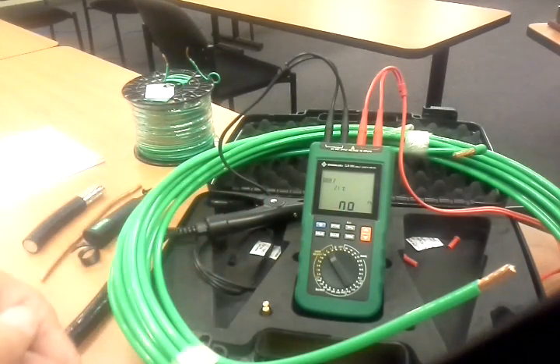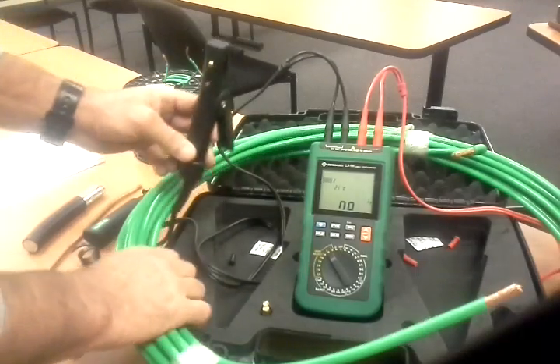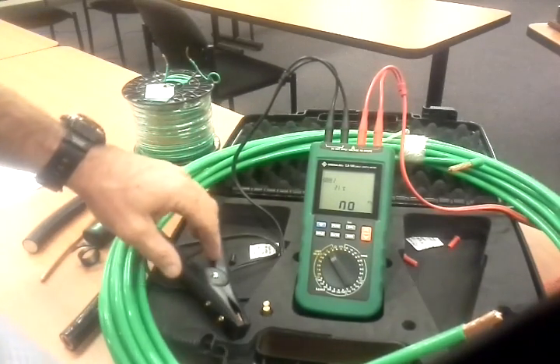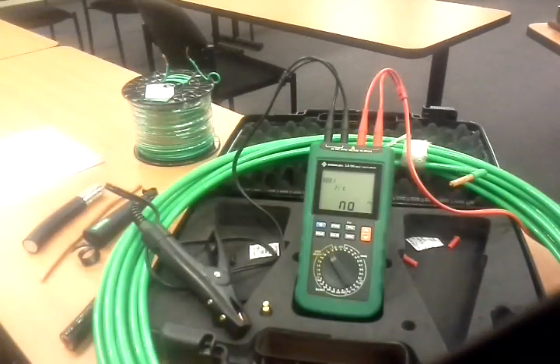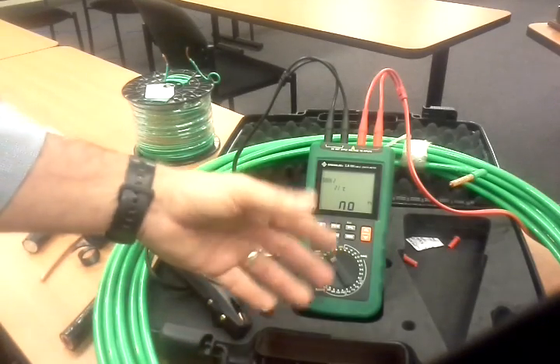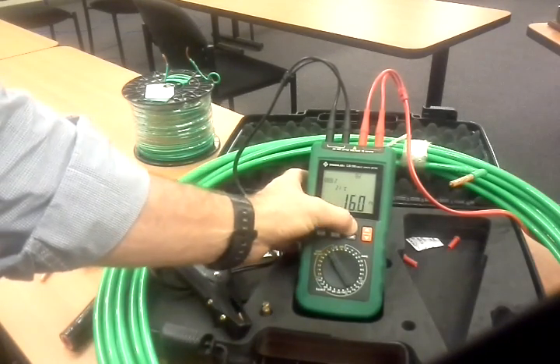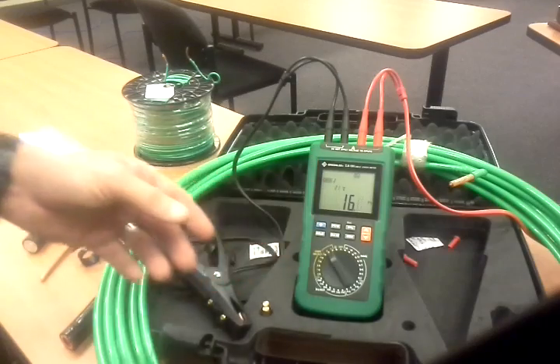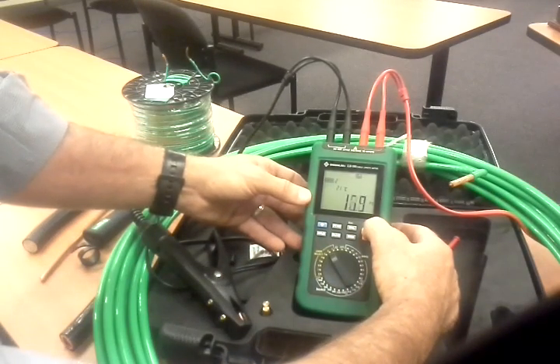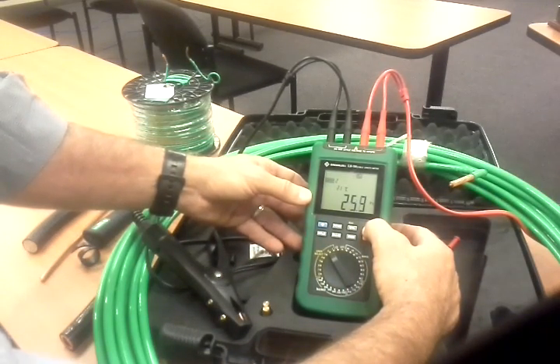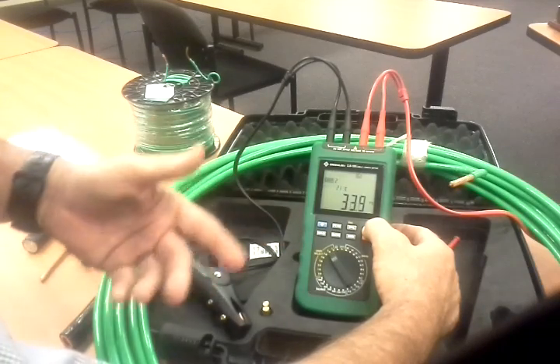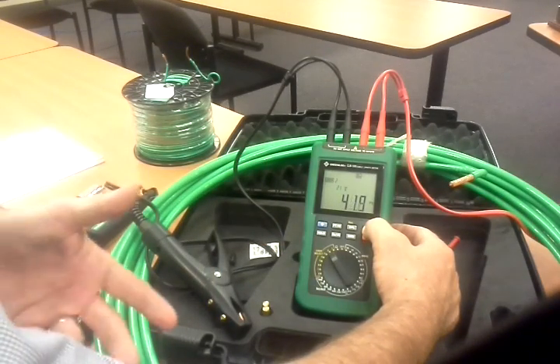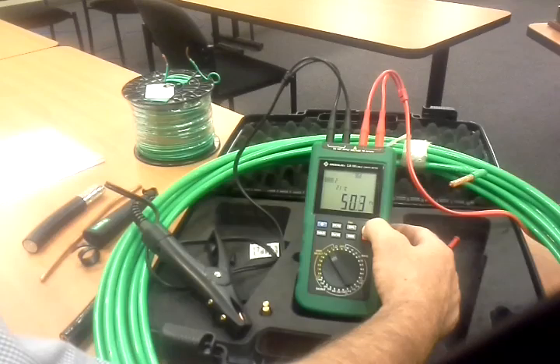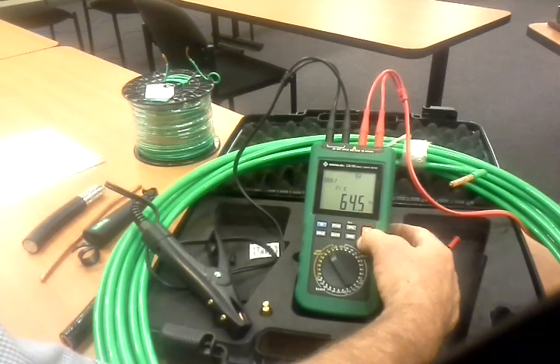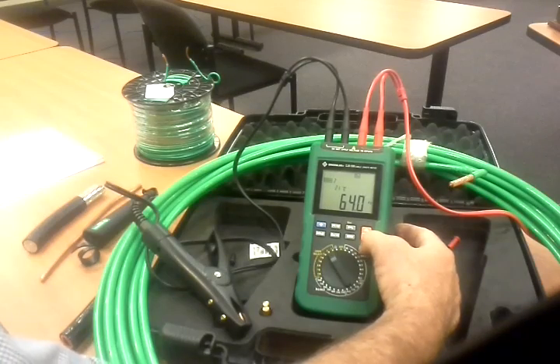So in order to set this now, all we have to do is go ahead and take the meter. And we already know the length of this is 64 feet. So we're going to want to set this so it's ready to go. So what we'll do is we'll press calibrate. And it comes up to 16. We're going to want to run this up to 64 feet. Once it gets to 64 feet, we'll press memory. The memory will show us that it's done. The 4 dashes will come across just like we did before in the calibration. We'll get it set to exactly 64 feet.